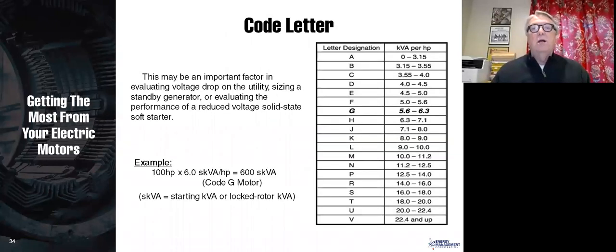Now this is a code letter. What is a code letter? That tells you starting kVA per horsepower. You know that when a motor starts, it takes approximately 6 times as much current to start as it does to run. And that's because the magnetic flux, when that rotor is at standstill, is going around the rotor at the full speed, let's say 1800 RPM. And so that creates very, very high currents in the rotor, which reflect to the stator. And so we end up with very high kVA.